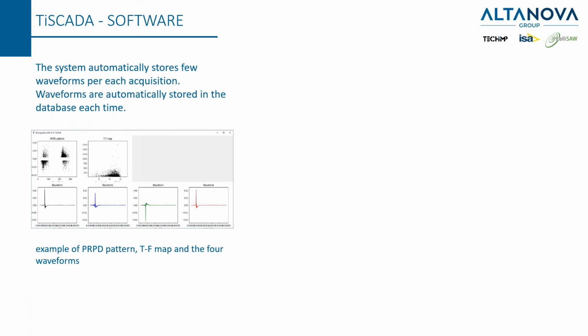Other few words about the SCADA. The system automatically stores a few waveforms, basically 4, per each acquisition. Waveforms are automatically stored in the database each time. These are 2 examples of PRPD pattern, TF-map, and the 4 waveforms.